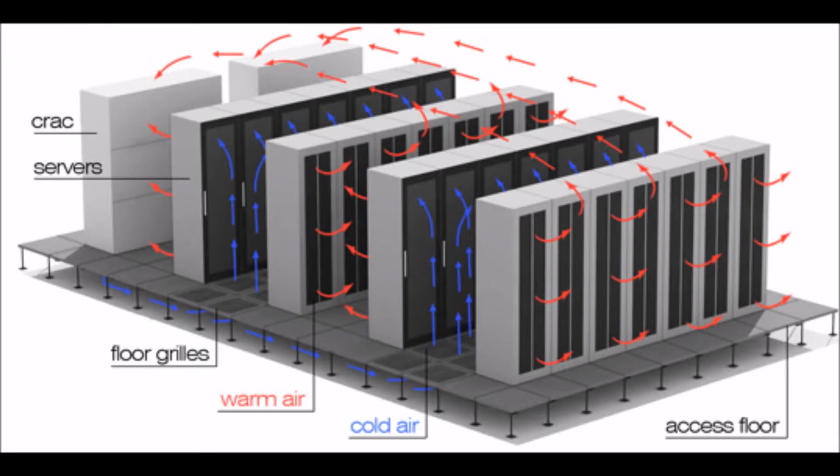Temperature distribution should be thoroughly planned, because poor planning on this key factor will greatly decrease performance on the racks. A well-known and successful method for the distribution layout is the hot aisle/cold aisle method, which consists of maximizing the separation between exhaust air from the racks and the intake air surrounding the racks. Establishing cold aisles where the rack intakes are present and hot aisles where the rack exhausts are located will greatly reduce the amount of hot air that finds its way into the intake ports, which improves both reliability and performance of the racks.